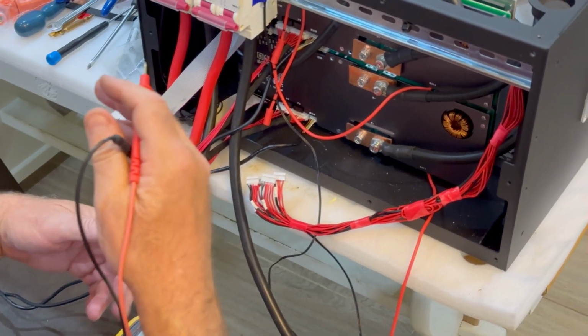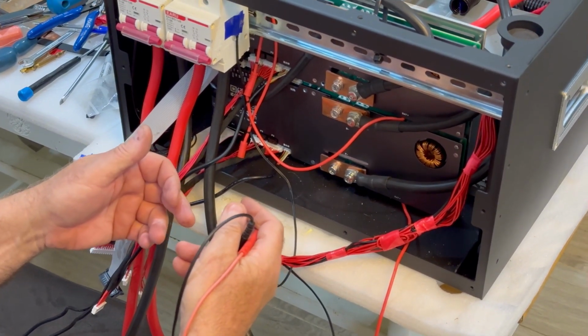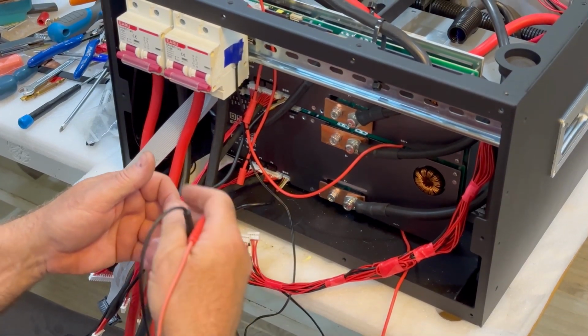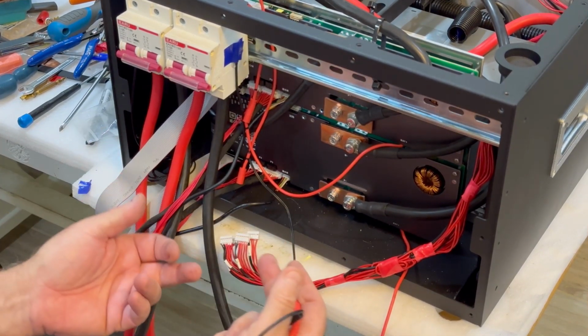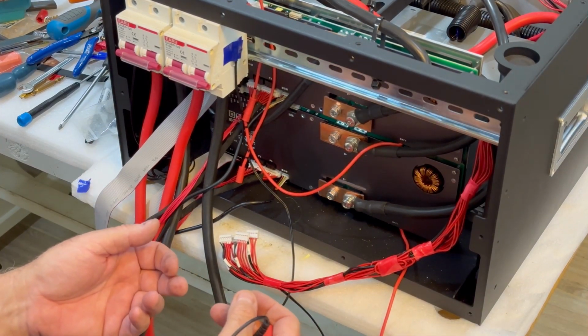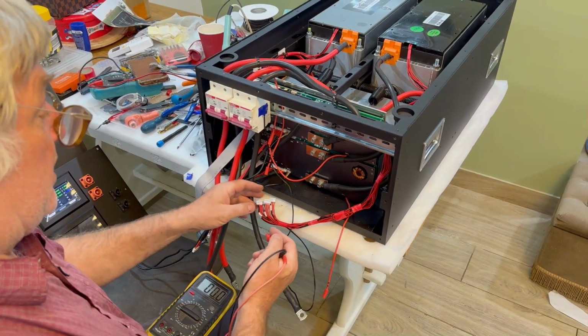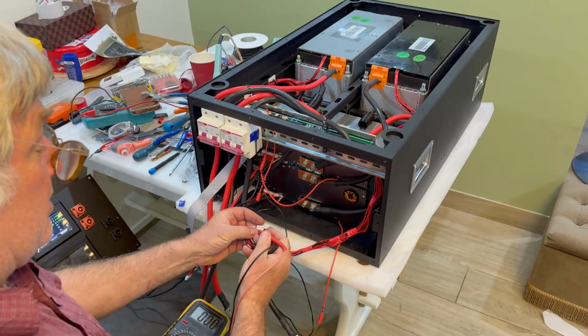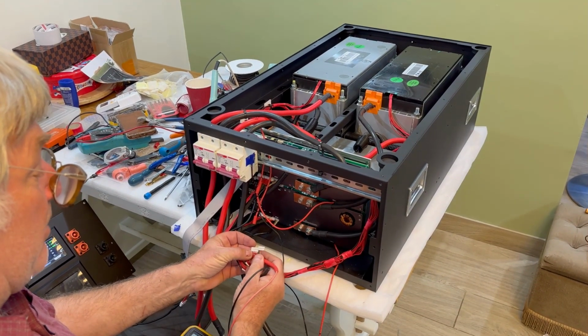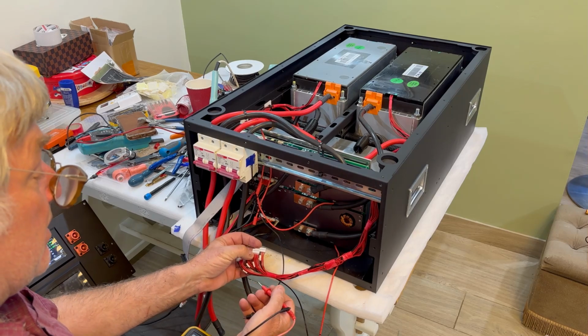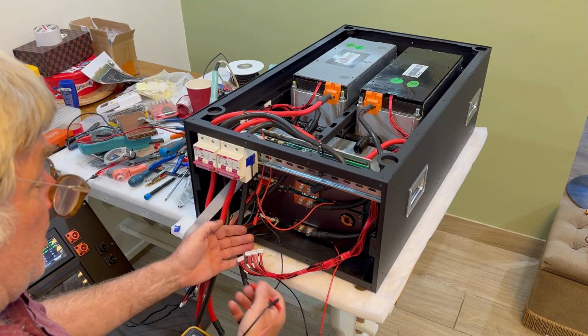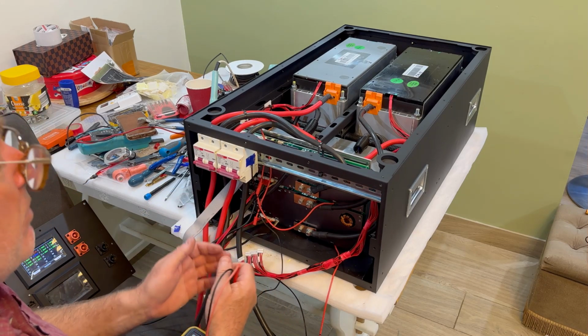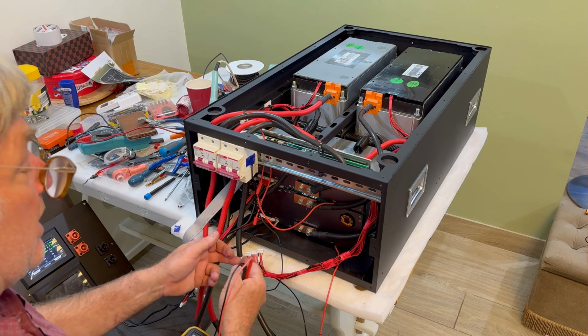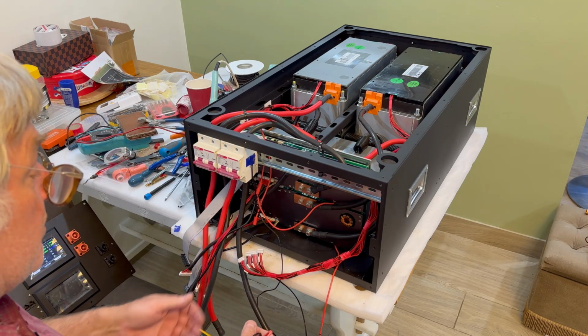If you suddenly find it reversed, where your cell voltage actually dropped, then you've got a cable in the wrong place, and it can be hard work sorting it out in there. In the past I have actually just dropped the cable out here and moved it to the correct point - not so much getting it wrong, but when I've changed the configuration of a battery and wanted to move the cables because I've taken cells off.